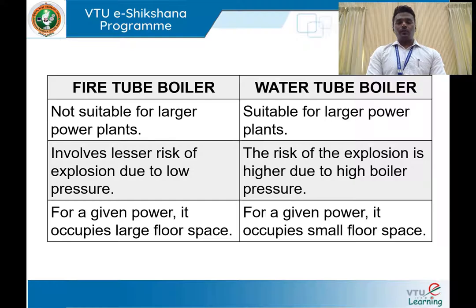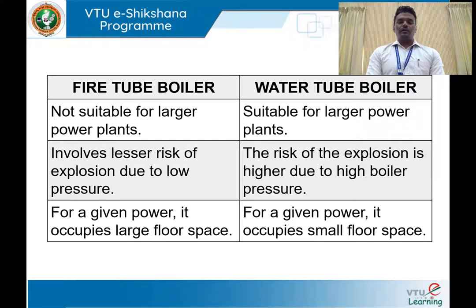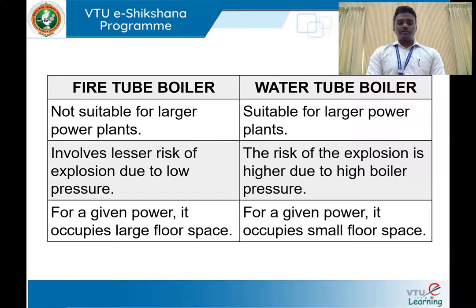To summarize the difference: in a fire tube boiler, flue gases flow inside the tubes and water passes around them. In a water tube boiler, water flows through the tubes and hot gases pass around them. Fire tube boilers generate steam at low pressure for low pressure applications, while water tube boilers can generate steam up to 100 bar for high pressure applications. Due to lower operating pressure, fire tube boilers pose less risk of explosion; water tube boilers carry more explosion hazard if not properly managed.